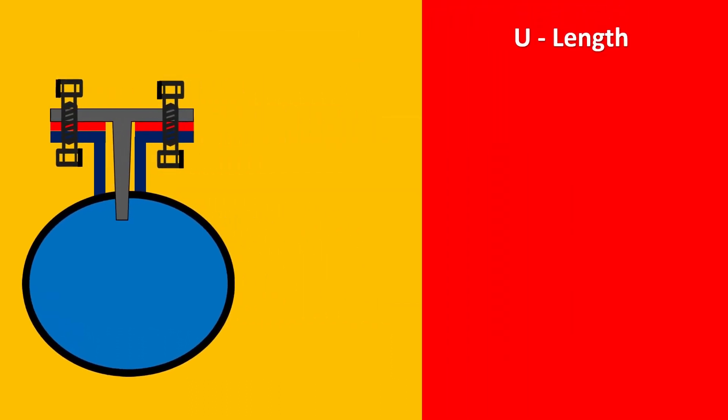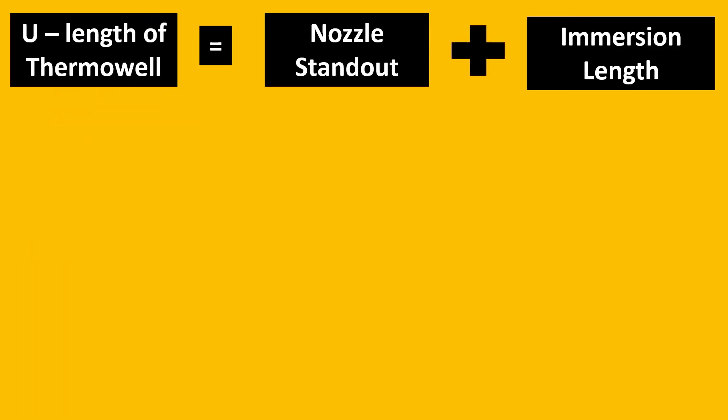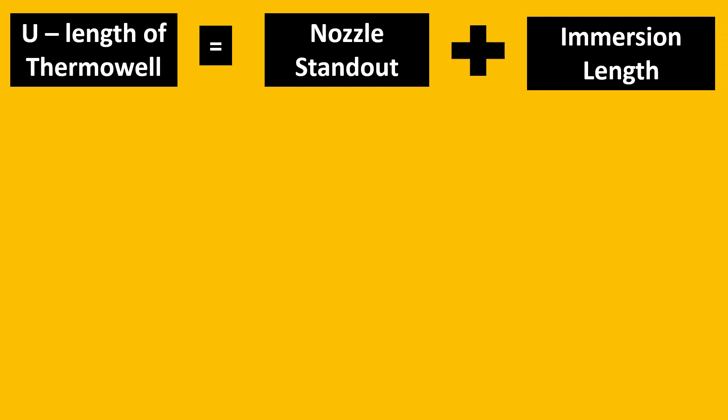Now to calculate U-length you need to know two amazing criteria: the immersion length and the nozzle standout. These are very important. Will you agree with this statement if I tell you that U-length of a thermowell is in simple words nothing but the nozzle standout plus the immersion length?